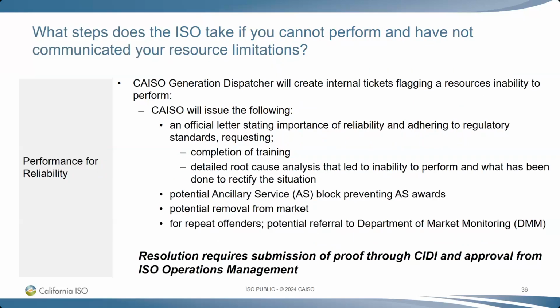Again, it's really about informing the market on what your resource is doing. Justin asked the question, and Brian, I'll hand this one off to you - are there particular times when you're allowed to be off AGC with regulations scheduled? No, anytime you have a regulation award, you should be on control. If you have any issues with your control system, you should have an outage in place, and you should be notifying the gen dispatcher that you are off control.